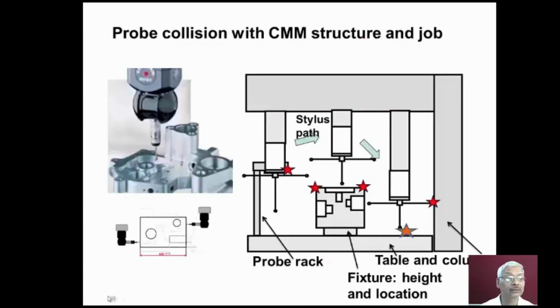Now let us try to understand how probe collision with the CMM structure or the job is avoided. We can see here we have the table of the coordinate measuring machine, and this is the column, and this is the overarm on which the probe head is provided. We have the probe fixed to the probe head, and this is the probe rack. Now this is the workpiece to be inspected, which is mounted on a fixture.